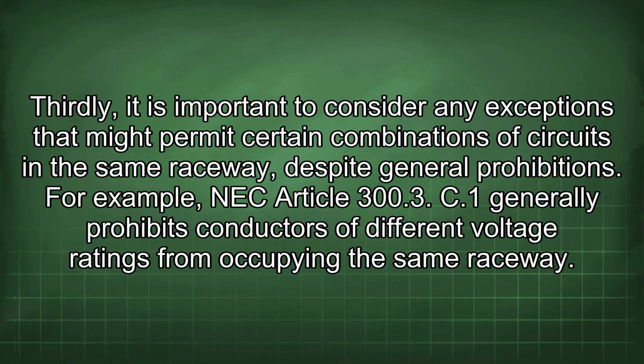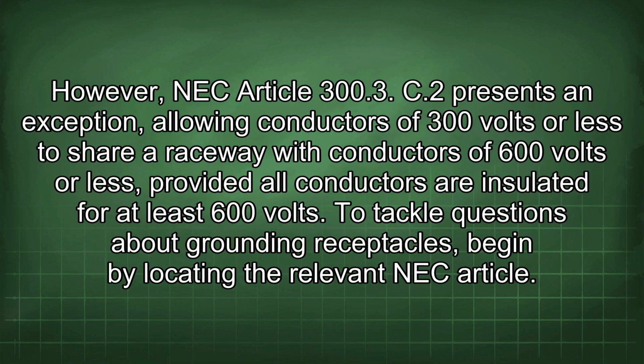general prohibitions. For example, NEC Article 300.3 C1 generally prohibits conductors of different voltage ratings from occupying the same raceway. However, NEC Article 300.3 C2 presents an exception, allowing conductors of 300 volts or less to share a raceway with conductors of 600 volts or less, provided all conductors are insulated for at least 600 volts.